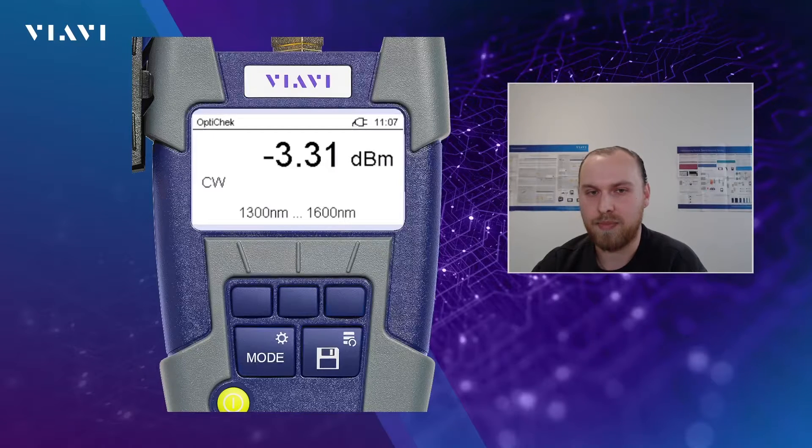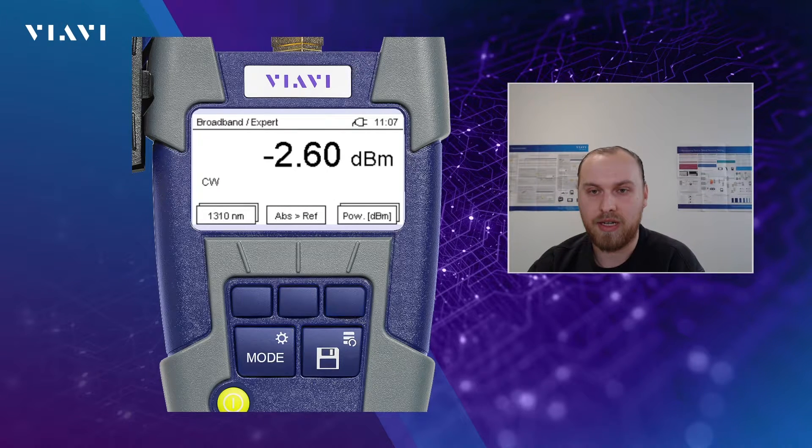Let's get deeper into the measurement. I have an OP35V2 connected via USB to my laptop, so I can use Smart Reposit to share the screen of the OP35V2, and I use an OLS 36V2 as a light source. Here we are in the OptiChek mode, that means the user does not need to select anything. You'll basically see an optical power shown on the screen in the single mode range, and if I change the measurement mode on the OP35V2 by pressing the mode key at the bottom, we get to the broadband or expert mode where we have more possibilities to change the settings.